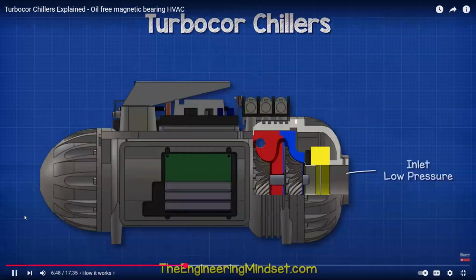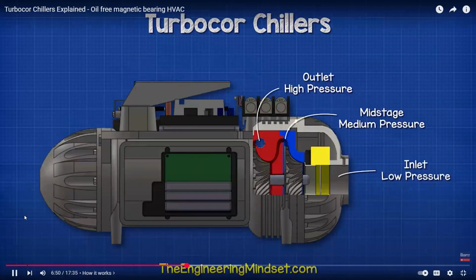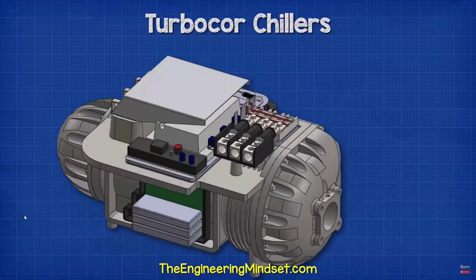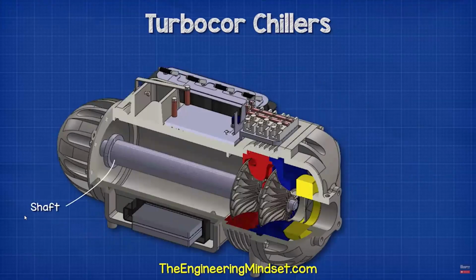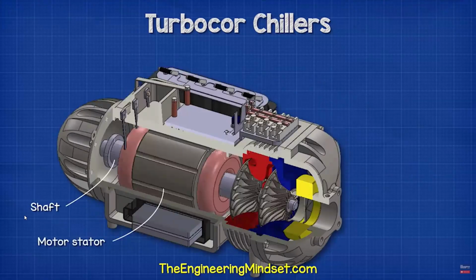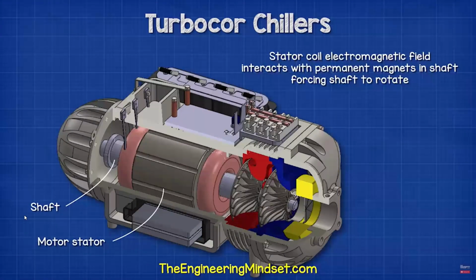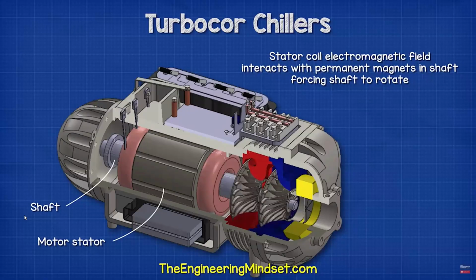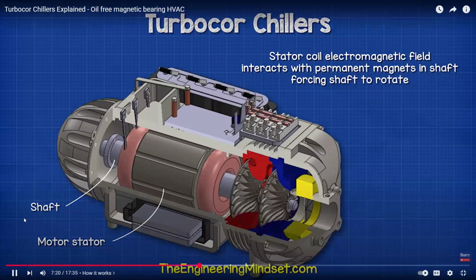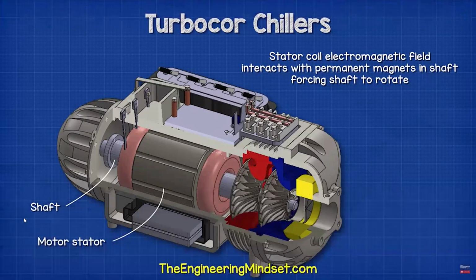The refrigerant pressure increases each time it passes through an impeller. The impellers are attached to the shaft, which runs the length of the compressor. The shaft passes through the electrical motor stator. The shaft contains permanent magnets in the rotor section. These will interact with the electromagnetic field produced by the stator coils of the motor. And because magnets attract and repel each other, we use this to force the rotor to rotate. The variable frequency drive controls the speed of rotation. The bearing motor compressor controller determines the required speed.